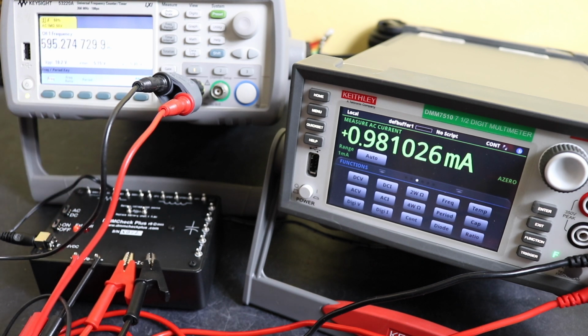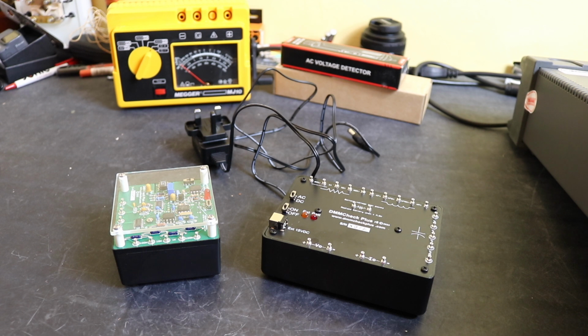Let's just flip it onto the 10 kilohertz, and we are now reading 0.98-ish milliamps. So yeah, not sure what the original problem was with that, really. It seems to be working fine now, which is obviously good, but I'm curious as to why we had the issue beforehand. That's all our testing completed, and we can have a look at the results.